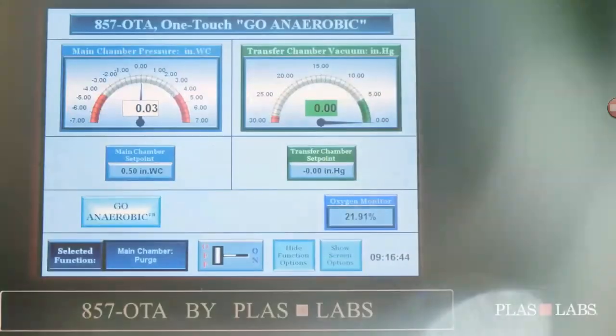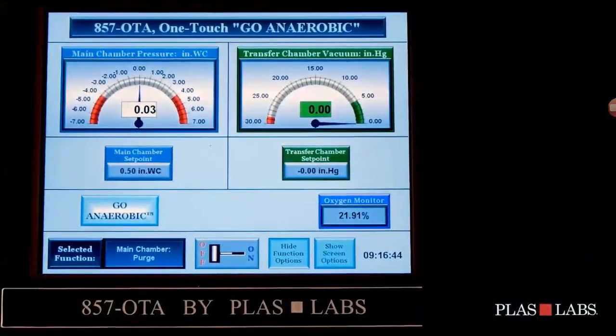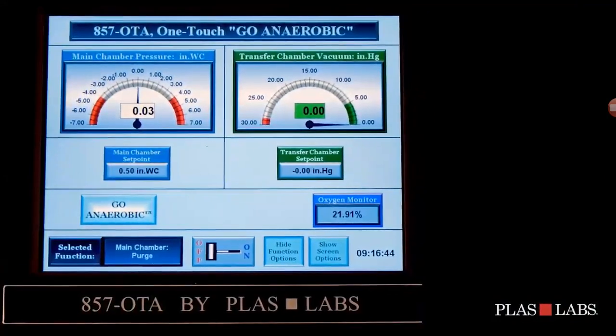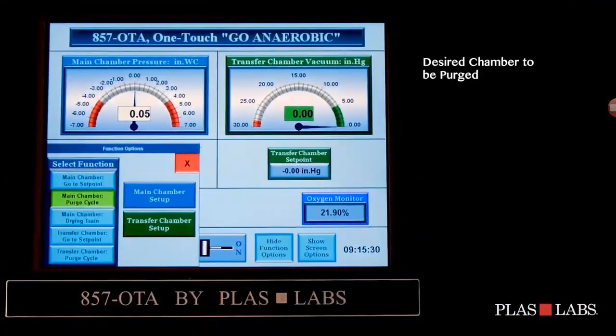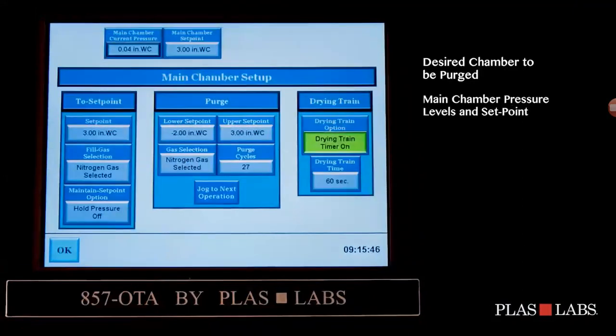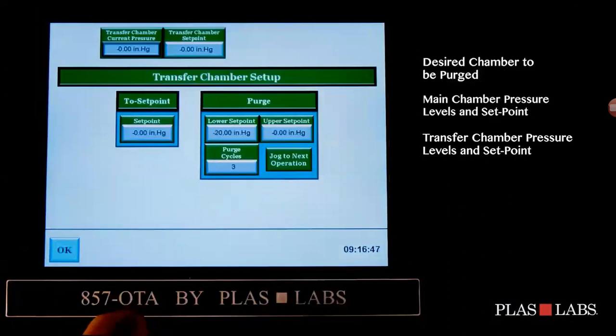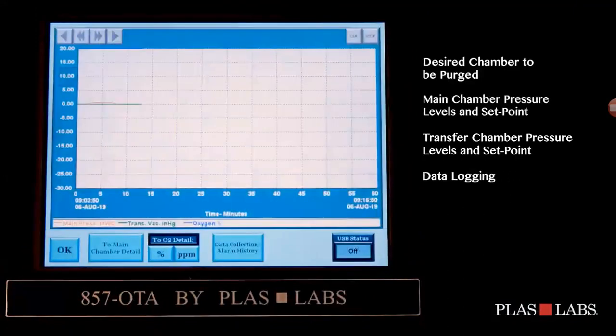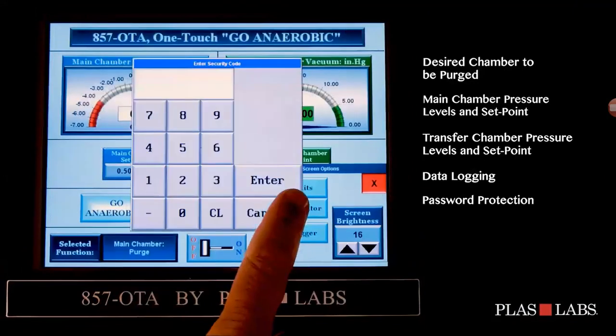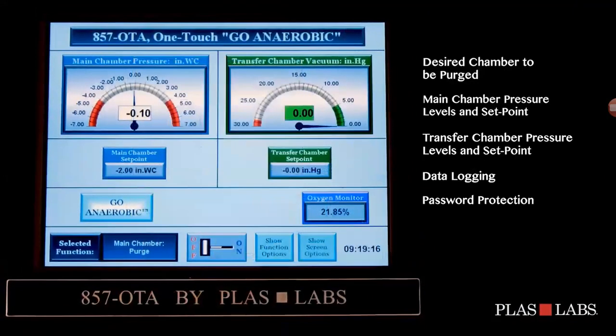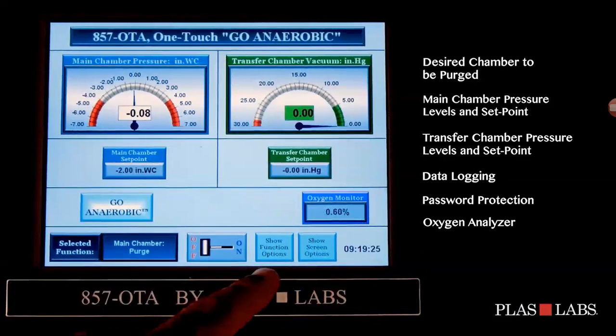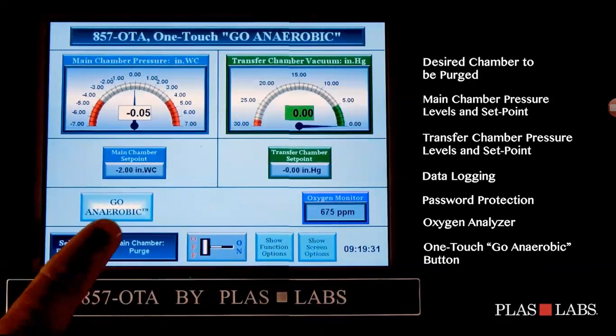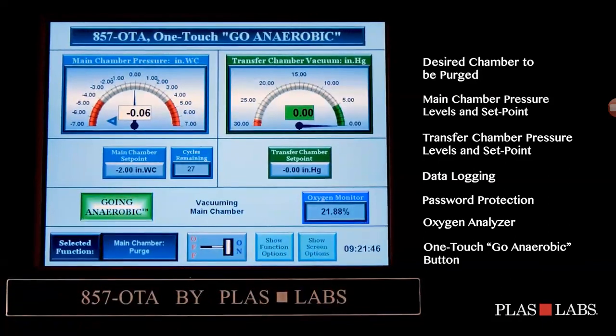The ambient conditions of your glove box can be seen on the touchscreen. The touchscreen display boasts many impressive features: desired chamber to be purged, main chamber pressure levels and set point, transfer chamber pressure levels and set point, data logging for pressure levels and oxygen, password protection, oxygen analyzer. The oxygen analyzer is designed to read a percentage value until the oxygen levels achieve less than 0.5%, at which time the oxygen analyzer will read oxygen levels in parts per million. And the one-touch Go Anaerobic button to begin the purging sequence.